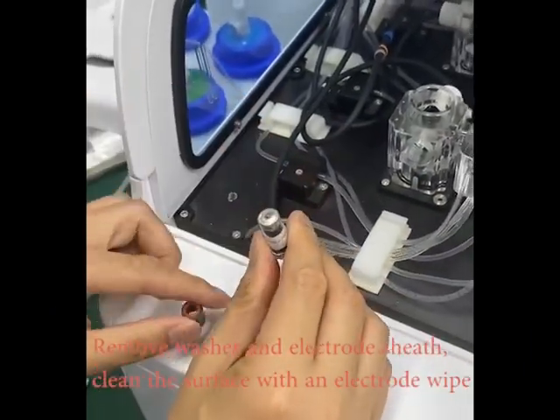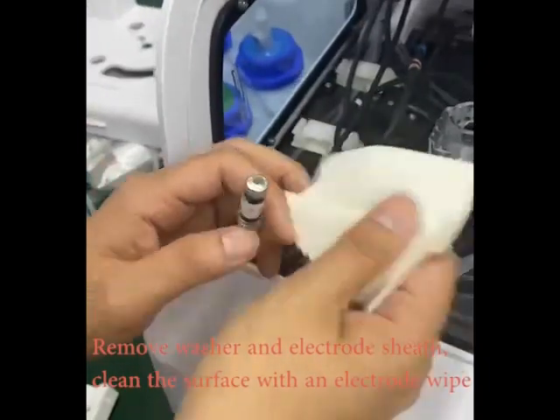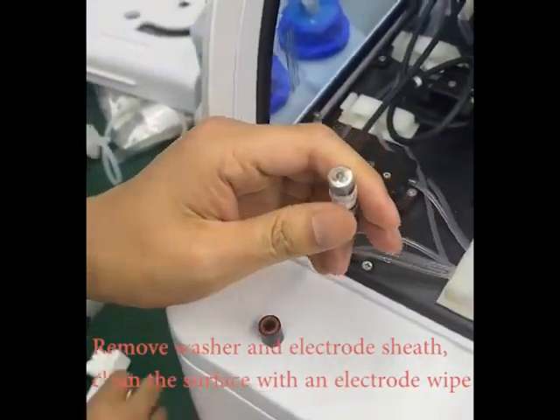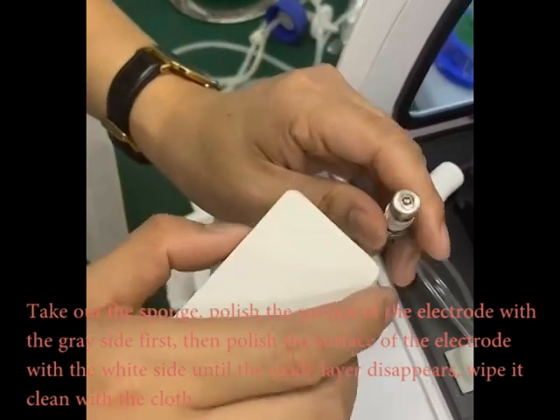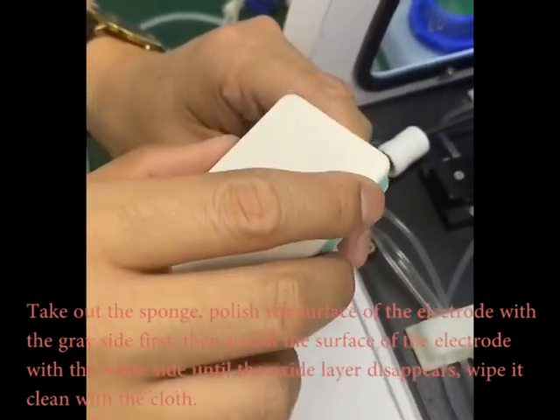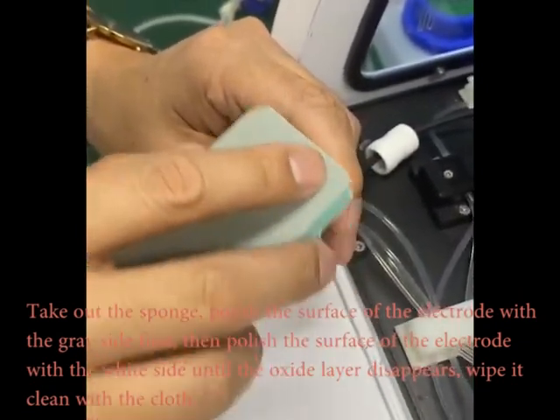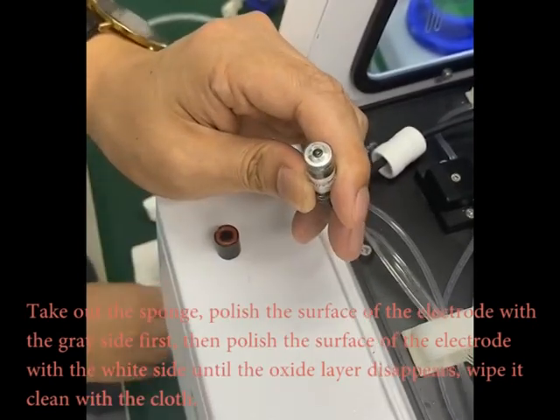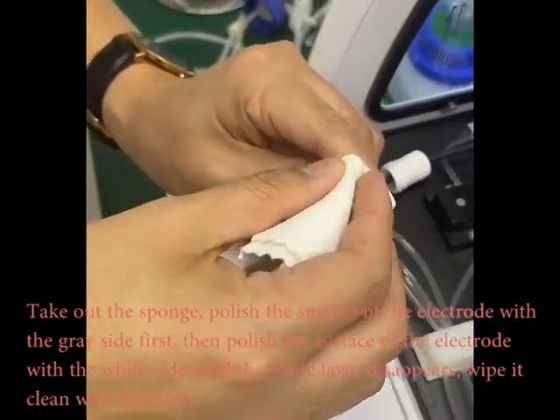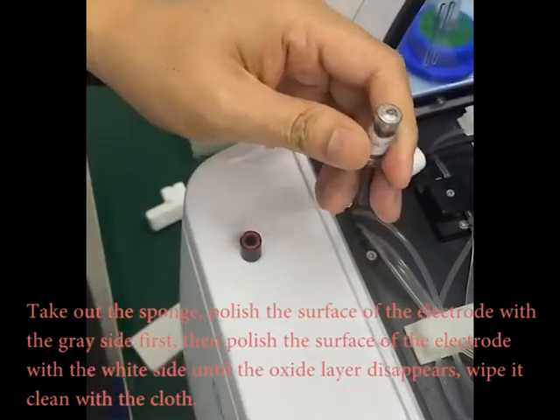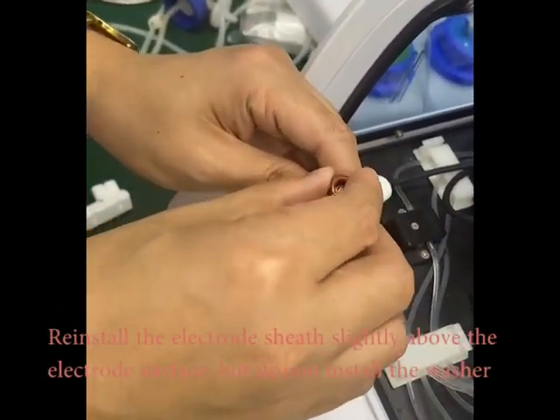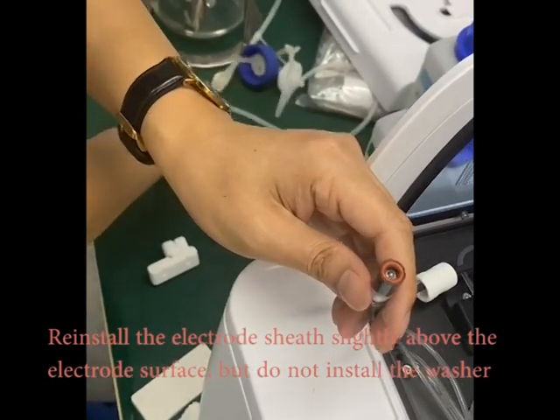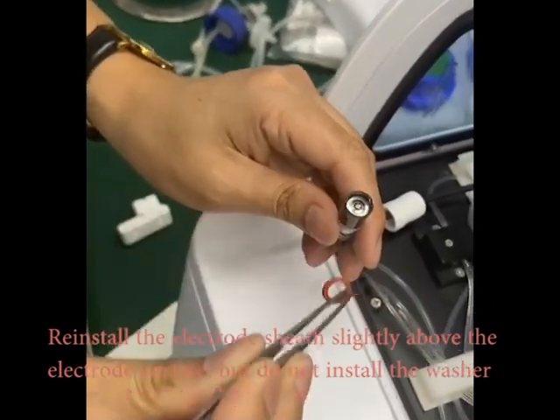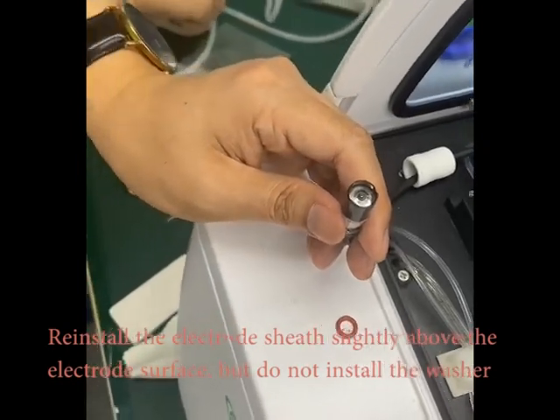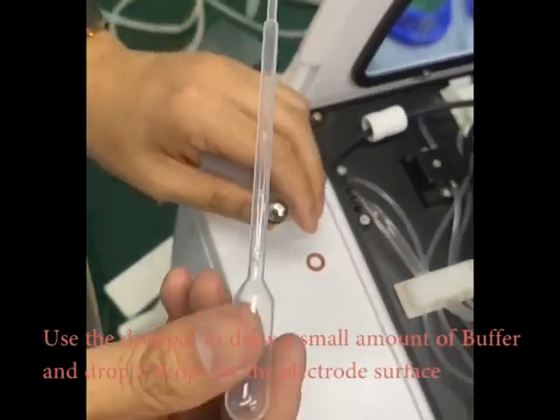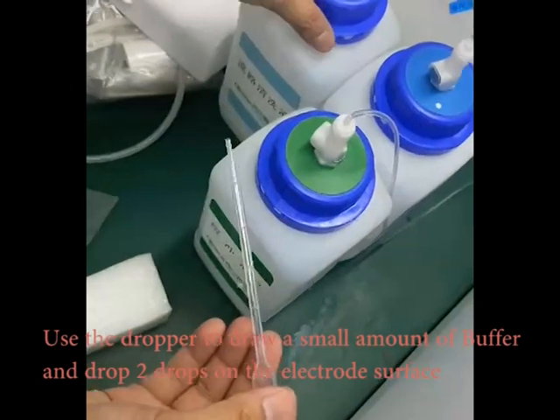Remove the washer and electrode sheath, and clean the surface with an electrode wipe. Take out the sponge, polish the surface of the electrode with the gray side first, then polish it with the white side until the oxide layer disappears, and wipe it clean with the cloth. Reinstall the electrode sheath slightly above the electrode surface, but do not install the washer. Use the dropper to draw a small amount of buffer and drop 2 drops on the electrode surface.